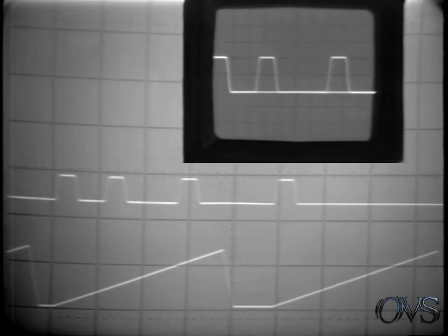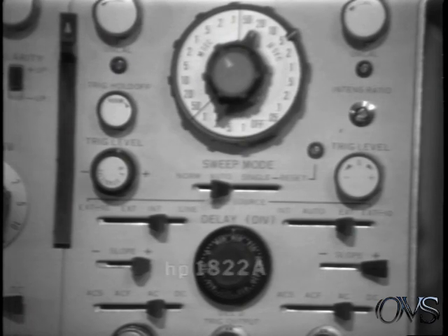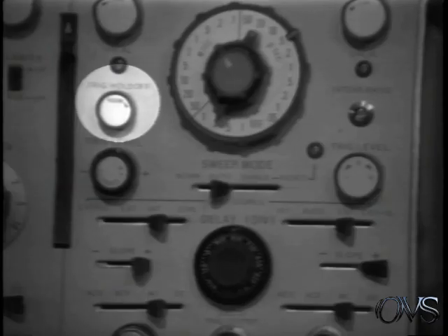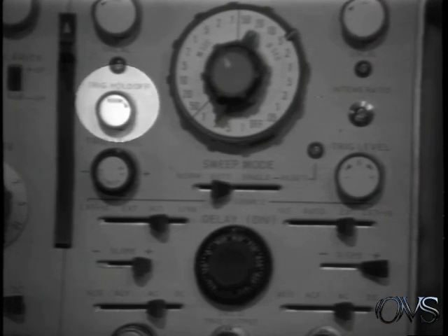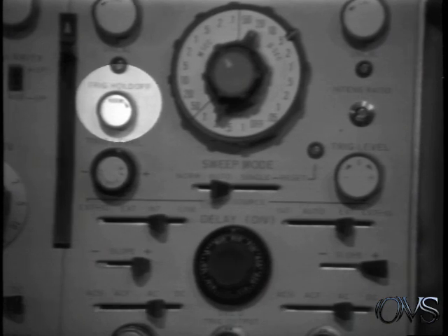So to overcome the instability, remember the criterion for a stable display to occur. That is, somehow the period from one sweep to the next must match the repeatable portion of the repeatable period of the incoming waveform. Some time-based generators, for example the 1822A, have a control on the front panel known as variable trigger hold-off. This control allows the operator to adjust the time between the end of one sweep and the beginning of the next, and therefore controls the period of operation of the oscilloscope.